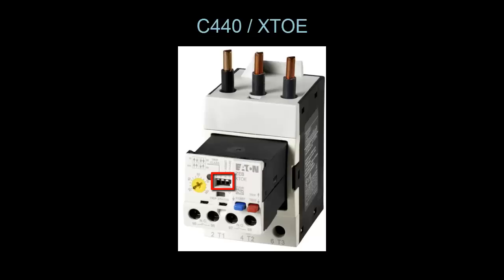This is a nice feature to have, whereas in a bimetallic overload, the heaters have a fixed trip class. So if you wanted to alter the trip class, you would have to replace the heaters, if it even has that option.